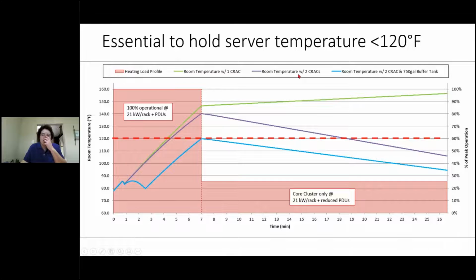In the end, we realized we had to store our own chill water capacity every day to have a reserve capable of covering us for those 6 minutes while the migration was going on. The simplest solution was actually to put in a 750-gallon buffer tank, because we had in-row cooling, so all we needed was a source of cold water and pumping - really low temperature, really low amounts of kilowatts imposed onto the generator.